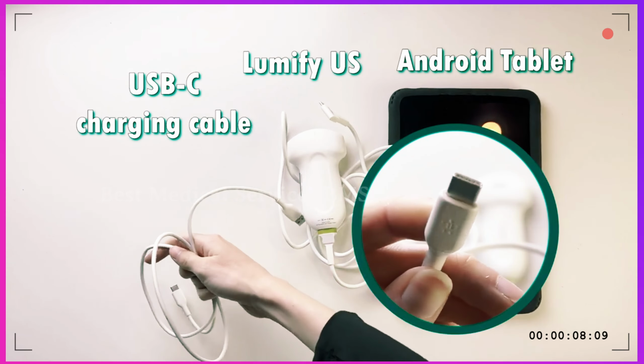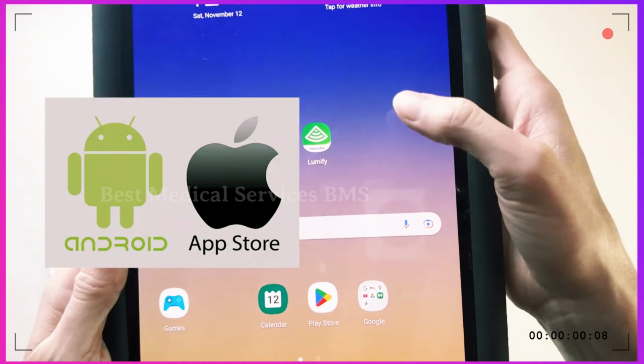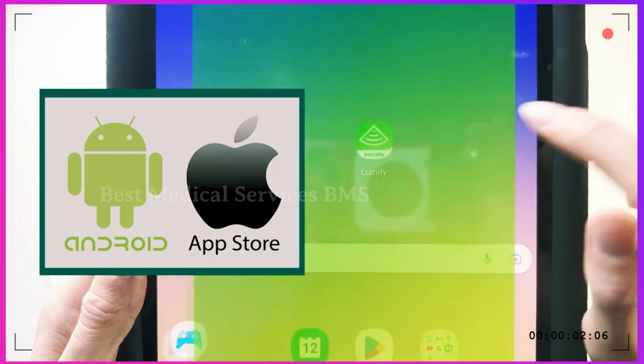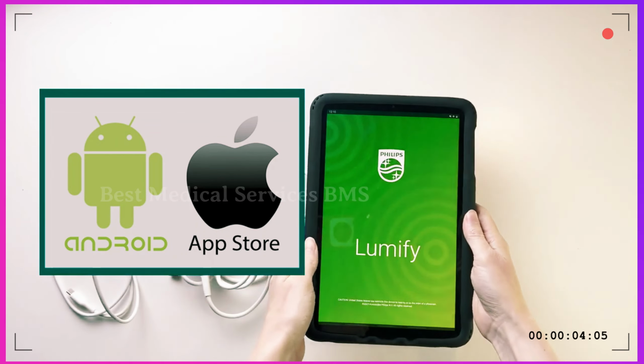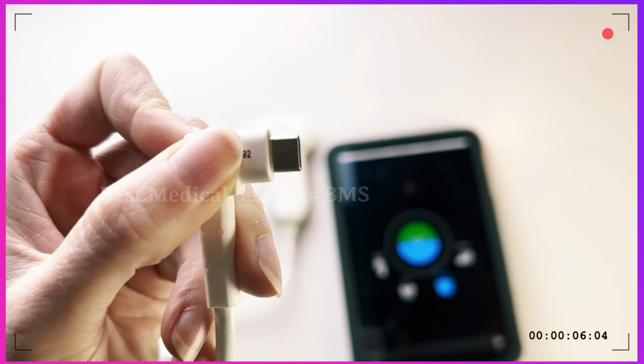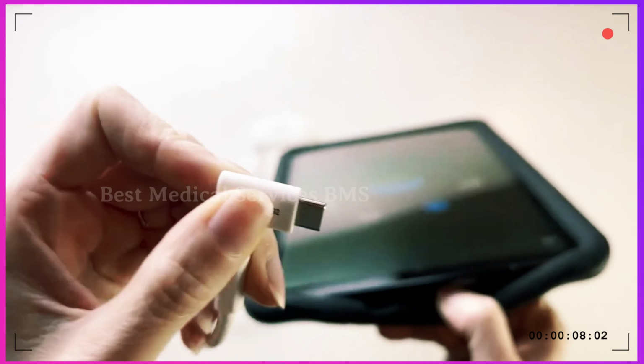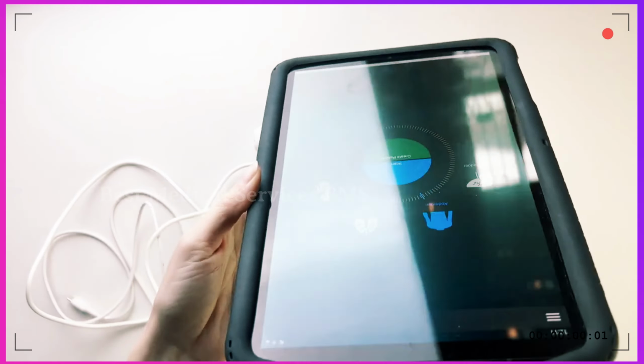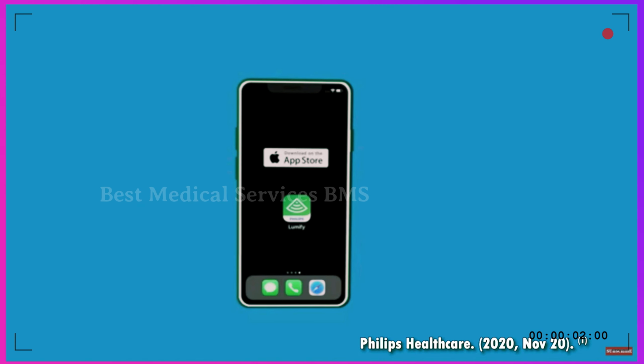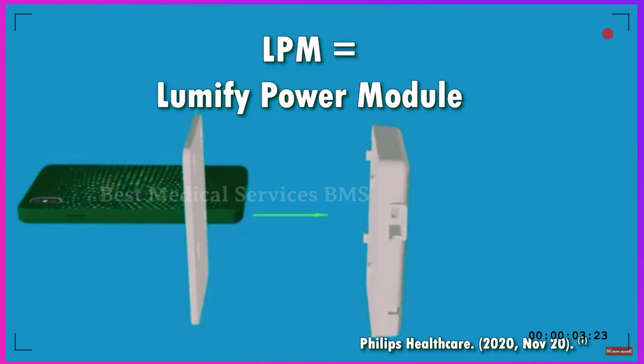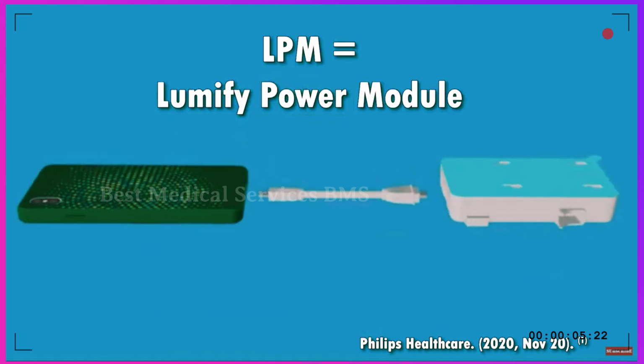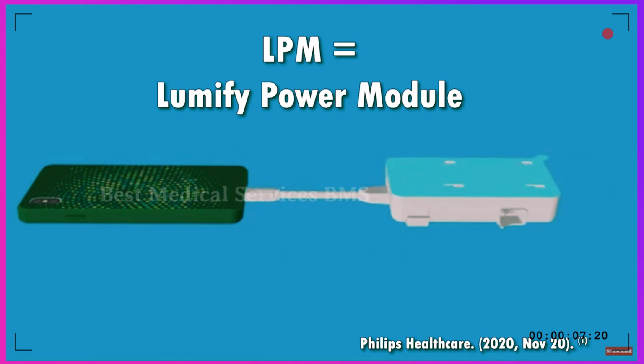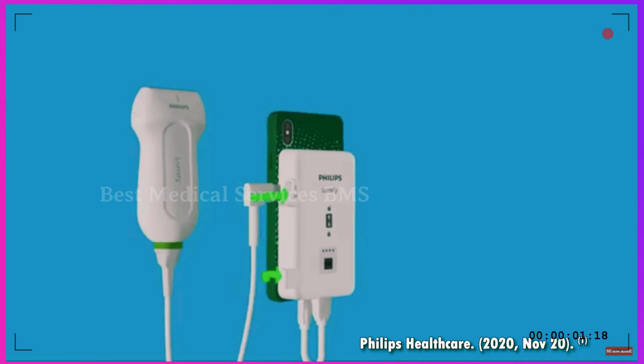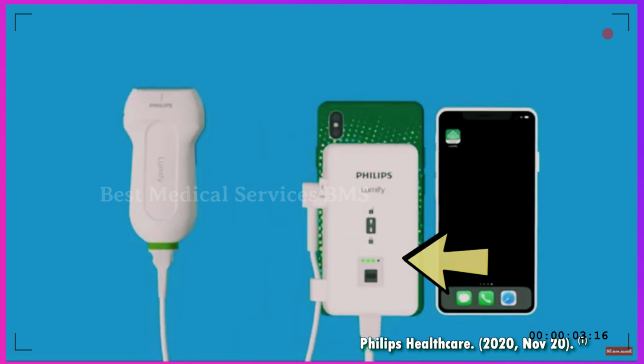The device is technically supported by both Android and Apple. However, it strongly favors Android devices because the Lumify does not have an internal battery, and it requires power from the USB-C. If you do have an Apple device, you will have to use something called an LPM, which is a Lumify Power Module. It's basically an external battery with a lightning connector. Once you hook that on, it works just like normal, and it does have a battery level indicator.